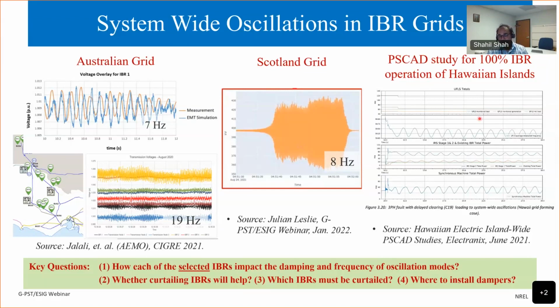Several EMT studies done to understand how we can operate power systems with large amounts of IBRs approaching 100% have also shown that oscillations or small signal stability can be a huge barrier in achieving that goal. For example, this study from Electranix on operating Hawaiian Islands with 100% IBRs showed this problem. So whenever a system planner sees this problem in EMT simulations, or a system operator sees it in the field, the question is where these oscillations are coming from, and which IBRs are creating them. Is it one or two specific IBRs, and can we curtail some of the IBRs to eliminate these oscillations? Which IBRs must be curtailed?